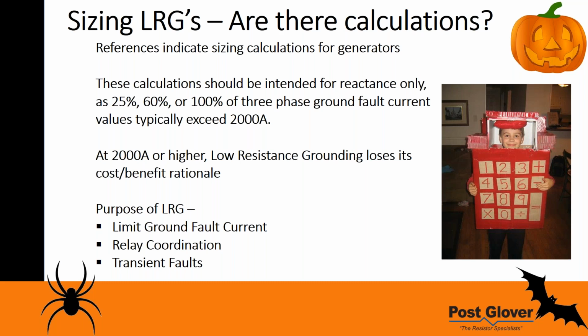If you're just looking to get the bare minimum of protection, you probably don't want a neutral grounding resistor, because above 2,000 amps is when those things get really expensive and big. Essentially you're transferring electrical energy into heat, but you're suppressing it. So if I have a 5 amp resistor, I'm only getting 5 amps, but you're turning that energy into heat. So the point is, 2,000 amps and above, we're looking at big NGRs, and that's really where a reactor is more sufficient.